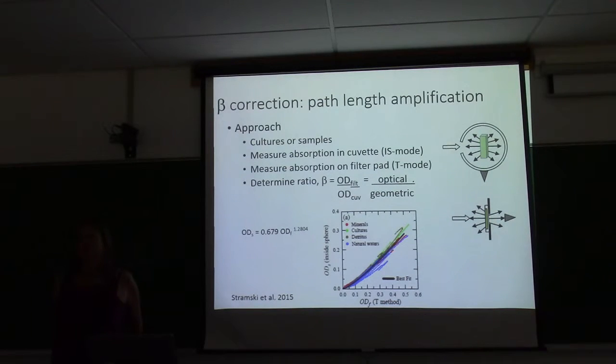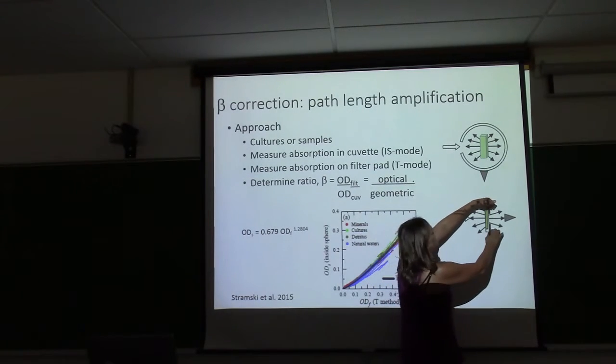For example, historically, I used to have an Aminco-Bowman spectrophotometer that had a beam scrambler. Some of that scattered light was collected by this long rectangular path that had a mirror. The light exiting the slit would get bounced around and hit the photomultiplier tube, so you would capture some of that scattered light. It captured all of this.